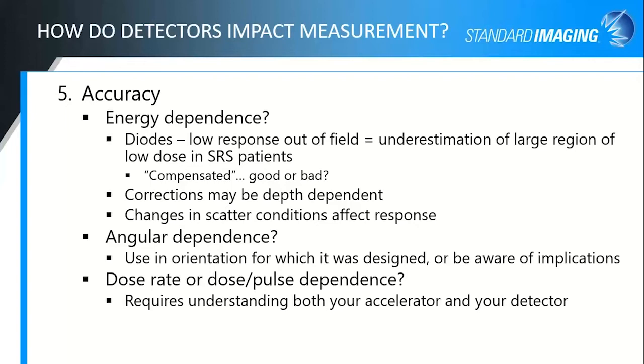There can be dose rate or dose per pulse dependence from your detector. This requires understanding both your accelerator and your detector. Some accelerators change the dose rate, just decrease dose rate just by dropping pulses rather than changing pulse height to go from one dose rate to another. But that's something that you would need to be aware of, how your system behaves, so that you know what sort of corrections you may need to apply for your detector.